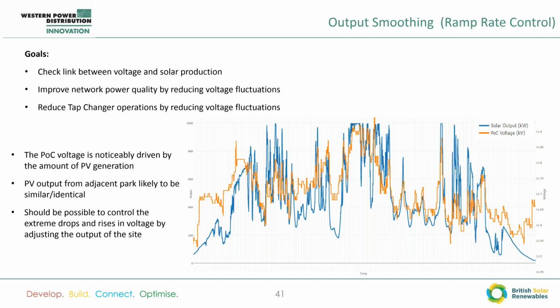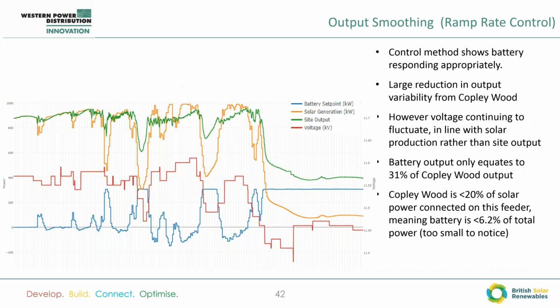The bigger gap on the left and just off the edge on the right there, we believe is the tap changer changing at Millfield at the end of the day when the generation drops away. So that's why there's a big gap there. But most of the time it's following very, very closely. These voltage fluctuations reduce power quality, and ramp rate control can reduce these fluctuations and reduce tap changer engaging, and therefore reduce the cost of maintenance of those.